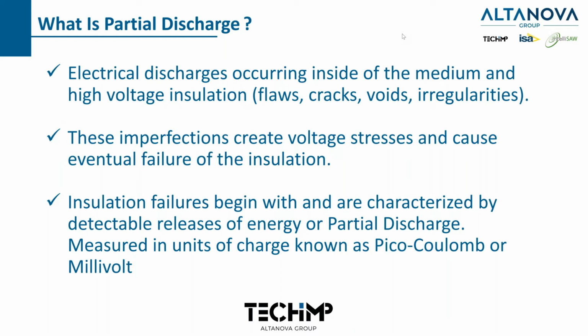With that being said, you should be asking yourself what we're actually measuring. So our equipment goes in and measures the partial discharge. The answer is that when partial discharge happens, it emits RF signals. And through the amplitude and frequency of these RF signals, we can determine the danger of that partial discharge. So the key here is when we go in to measure partial discharge, we're measuring RF signals.